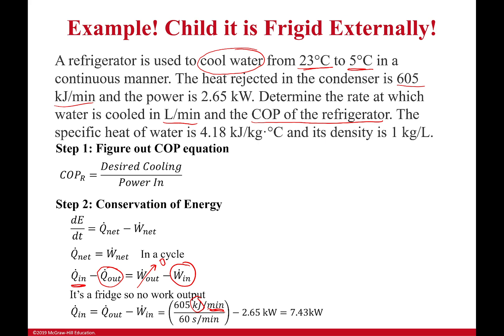So that's how much heat is being input from the water to the refrigerant. Because of that, I can get my coefficient of performance - it's 2.8. Is that good? It's passable.